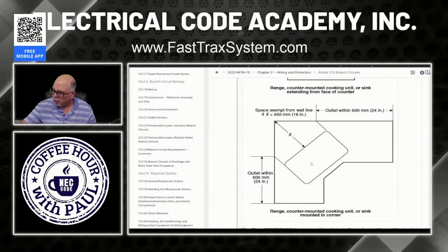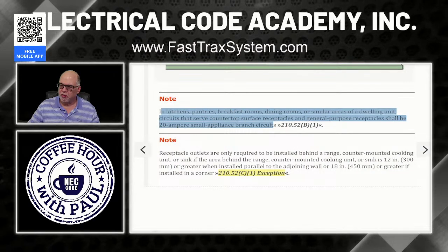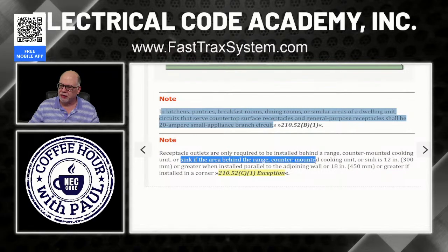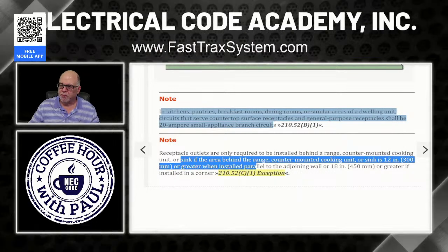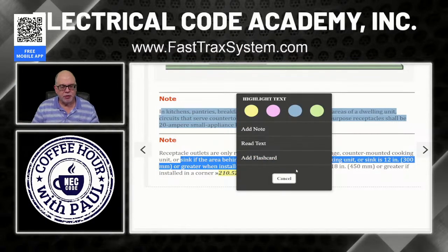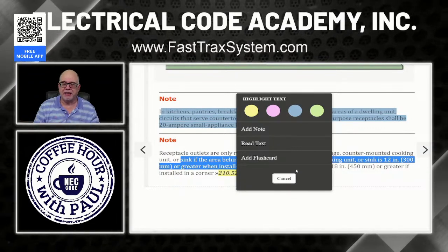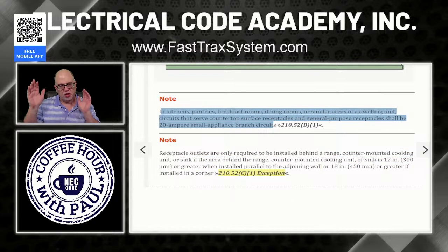Okay. So bringing us back to our course material, that's what it says right here. Right? So a sink behind our range or cooking counter mounting unit or sink is 12 inches or greater, okay? Where installed parallel, again, if it's 12 inches or greater, then guess what? I have to put a receptacle. It's just part of the wall space. So I have to count it, and I might get a receptacle back there, okay? Still got to do the 2 foot, 4 foot. If it is less than 12 inches, ignore it.